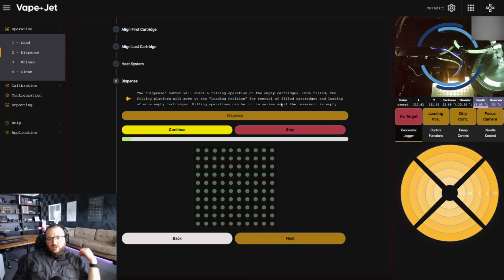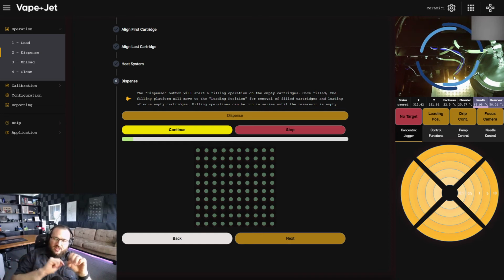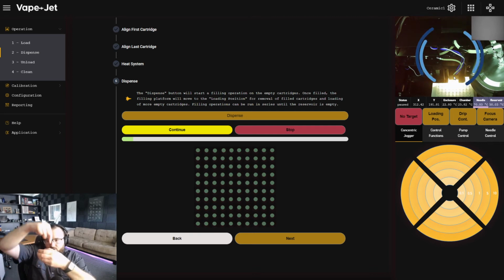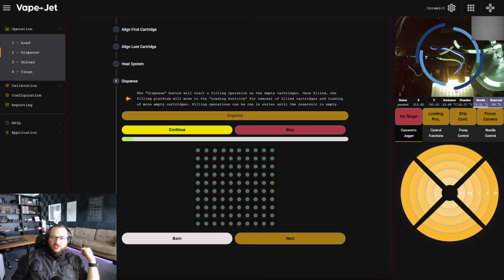When I hit continue, the pump moves forward at the same time the needle retracts from the system. See that? It slowly pulled out of the cartridge as it pushed the fluid in. Those movements are timed together so that the very tip of the needle never hits the actual fluid level—it's always hovering just above it as you're filling the cartridge.